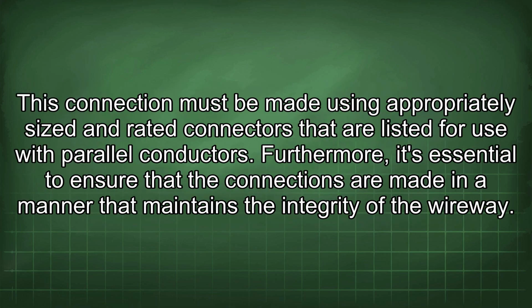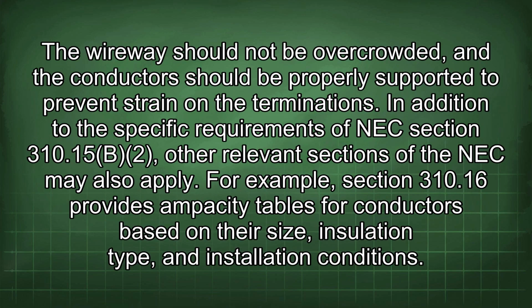This connection must be made using appropriately sized and rated connectors that are listed for use with parallel conductors. Furthermore, it's essential to ensure that the connections are made in a manner that maintains the integrity of the wireway. The wireway should not be overcrowded, and the conductors should be properly supported to prevent strain on the terminations.